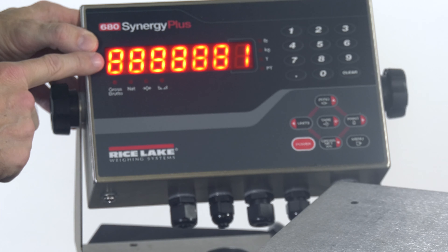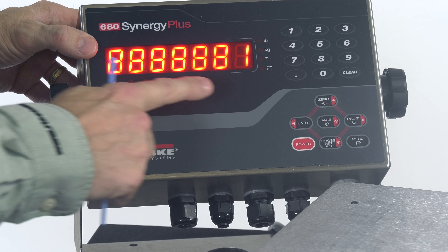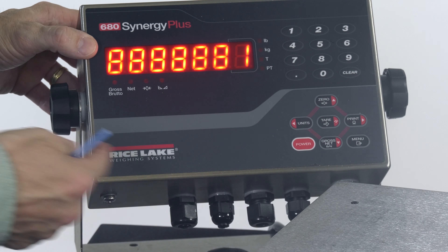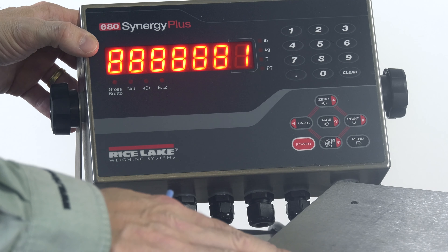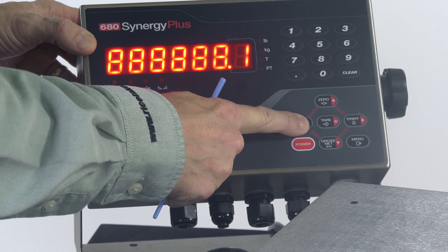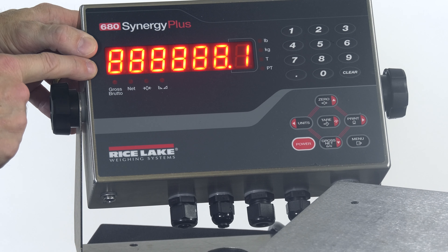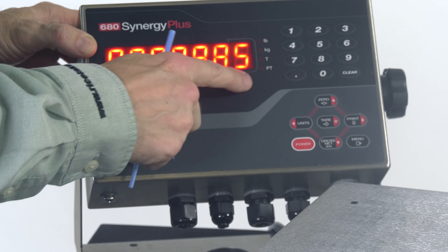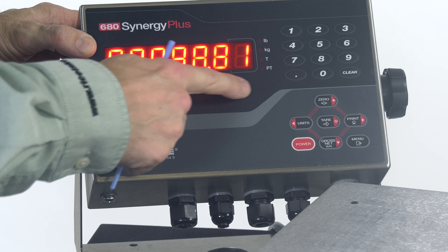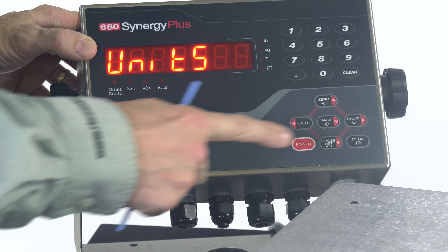From here I'll go back up with the 0 key, which brings me back to Config, and then I'll navigate to the right using the Print key, where I'll see Format on the display. From there I'm going to come down — I'll see Primary, which is indicating the primary units of measure; by default that's going to be pounds. I'll come down again and see Format a second time. Continuing to come down, I'll see a bunch of eights and then a number on the end. This tells me how my count-by is going to increment. By default, it's incrementing by one pound.